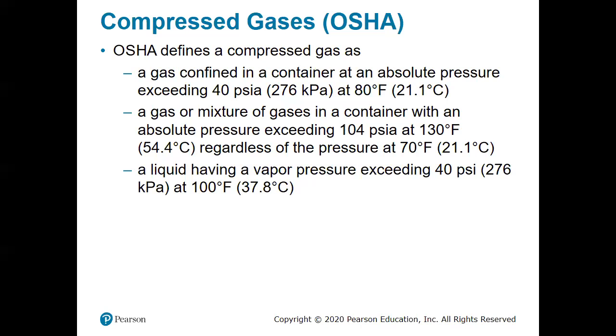So OSHA, Occupational Safety and Health Administration, they define a compressed gas as any gas confined to a container at an absolute pressure exceeding 40 psi at 80 degrees Fahrenheit. Or a gas or mixture of gases with an absolute pressure exceeding 104 psi at 130 Fahrenheit, regardless of what the pressure might be at 70.